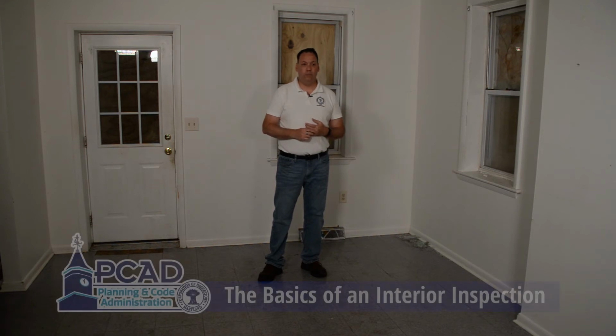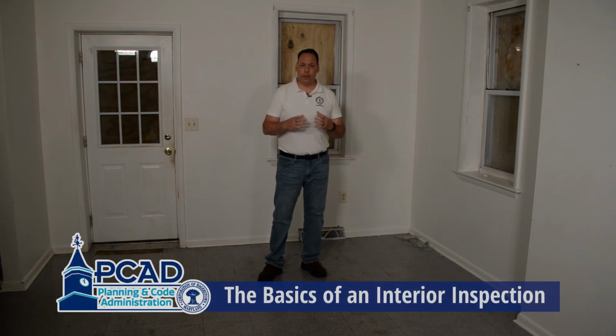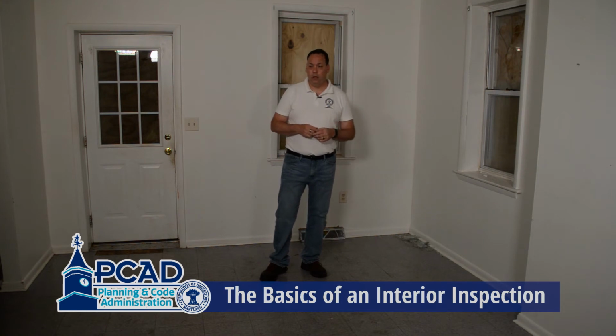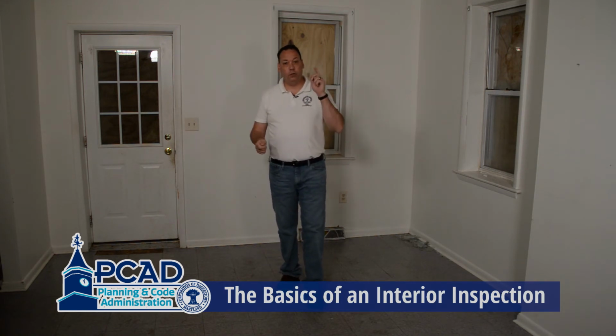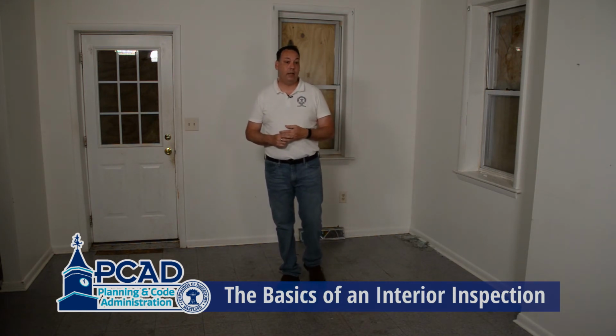And then also I'm looking at the light fixtures. So if there's light fixtures in the room, making sure that they're simply in good repair, they're working properly. The wire, there's no loose wire, the fixture itself is not loose. If the light fixture is made to have a globe on it to cover the light, we're looking to have that globe fixture on that. So just making sure that the light fixture is in good repair. If there's a remote switch, making sure that the remote switch works to operate that light.